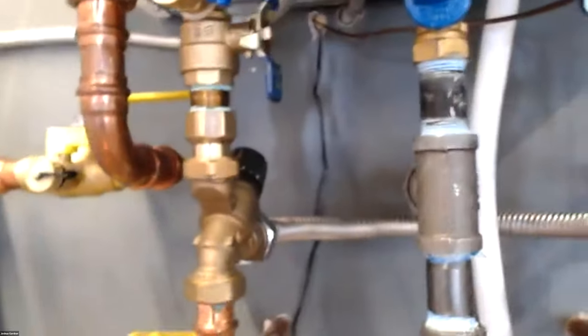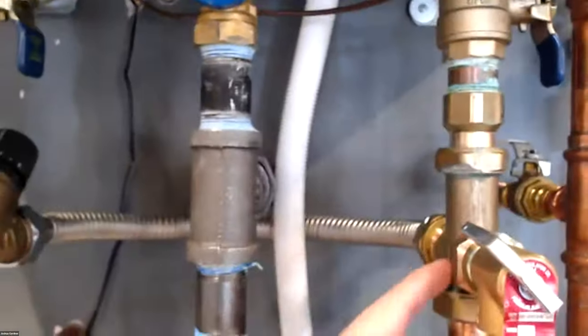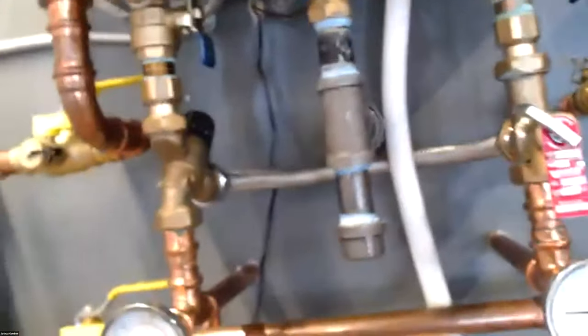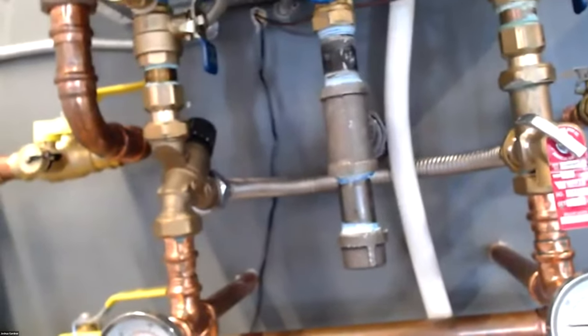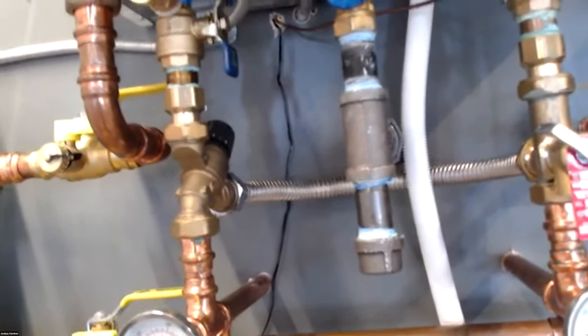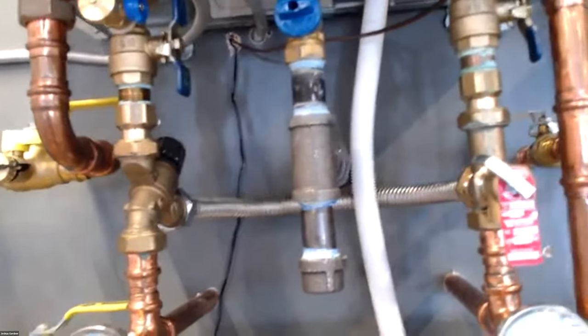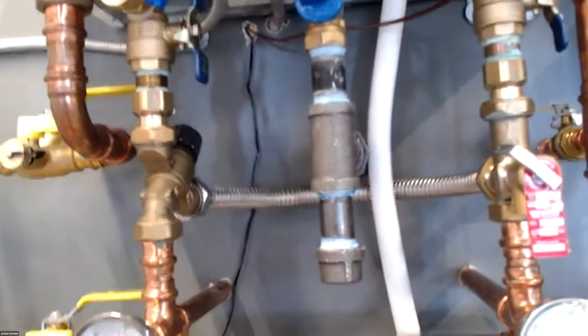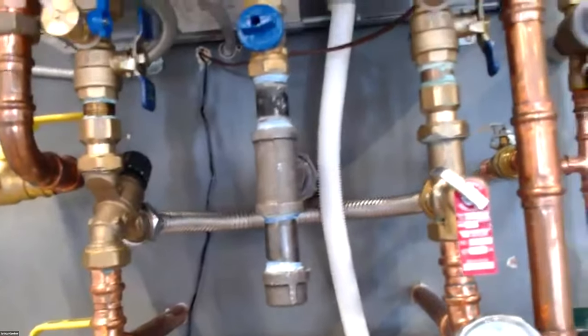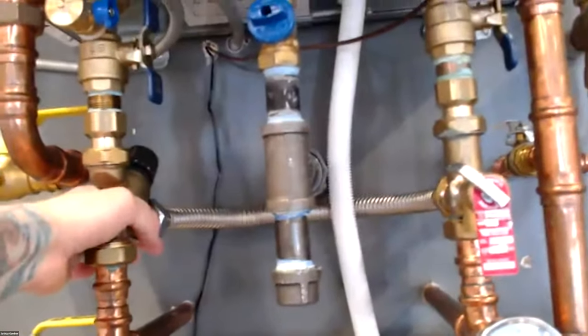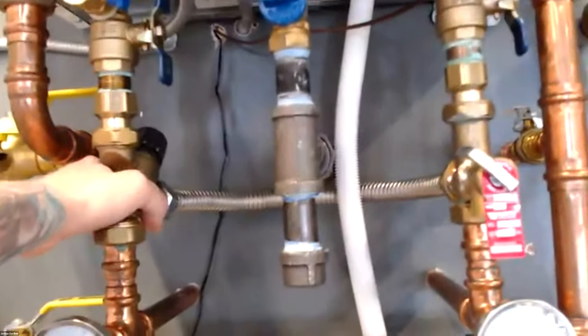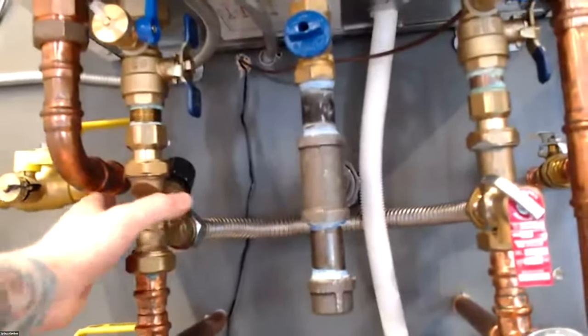This one you can see we're using one of those Caleffi crossover mixing valves, and then we have our flush valves up in here. So if you can run a mixing valve, that's great. It's just gonna give us a little bit more output, or the homeowner more output. It's also gonna help keep that flow nice and consistent. Our boilers on the domestic side and the combis coming out, it is steady. I won't say it fluctuates, but having this mixing valve in here just alleviates any issues if there are pressure issues or water quality issues in that house. They work great. Also, they're a good protection for kids if there is an issue.